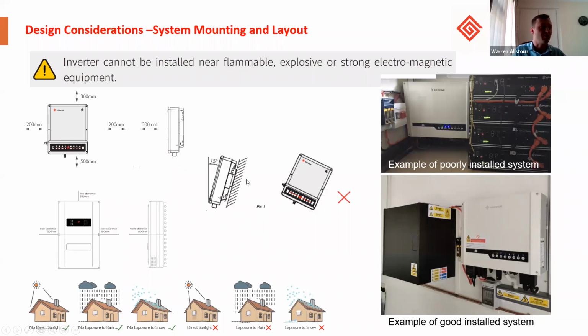Other important aspects to remember is the inverter must not be installed near flammable, explosive, and strong electromagnetic equipment. It needs to be out of direct sunlight, so a canopy, no exposure to rain, again, a canopy, and not so prevalent in South Africa, but not exposed to snow. On the left-hand side here, illustrating the correct manner to install it.